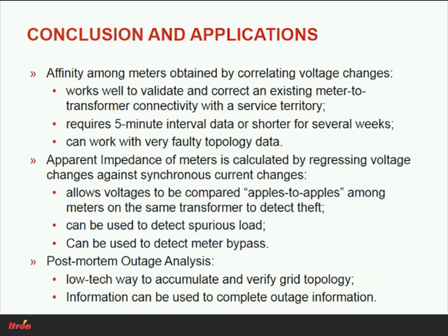Now, if the unmetered load, and that's somewhat related, if a theft, for example, occurred directly on the secondary of a transformer and upstream of all meters, I mean somebody taps directly into the transformer, which does happen, then of course all meters will have a lower voltage. And the only way to find that out is by comparing that transformer secondary voltage to that of other transformers nearby. And if you find a systematic deviation, that is at least an indicator.